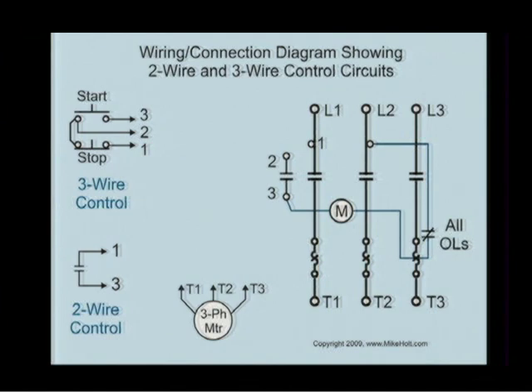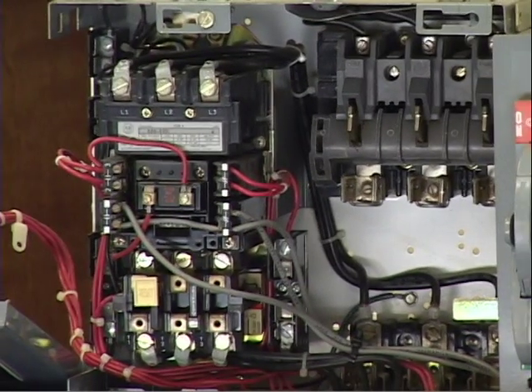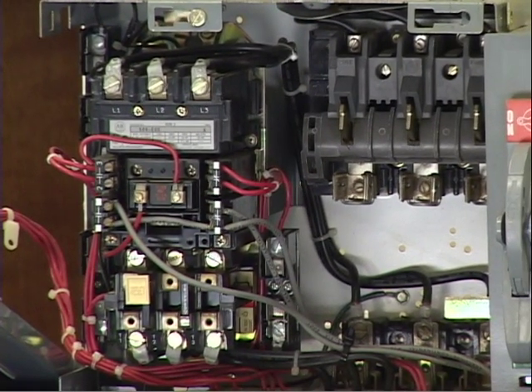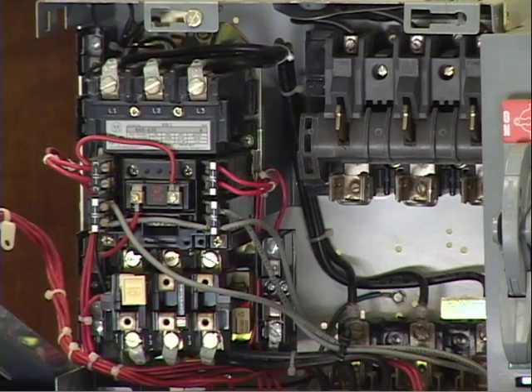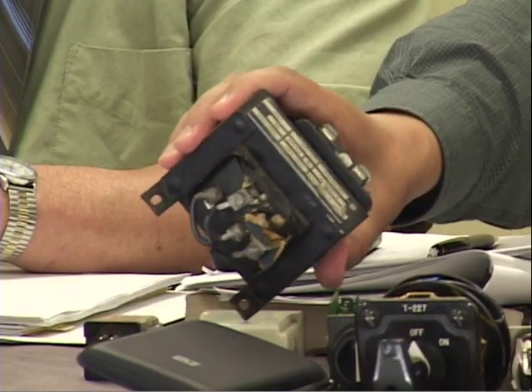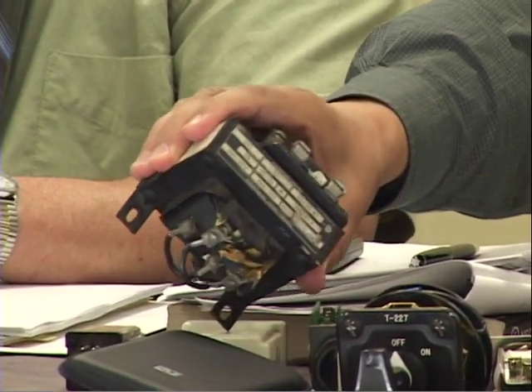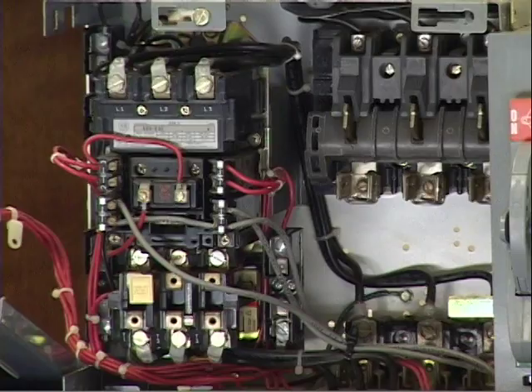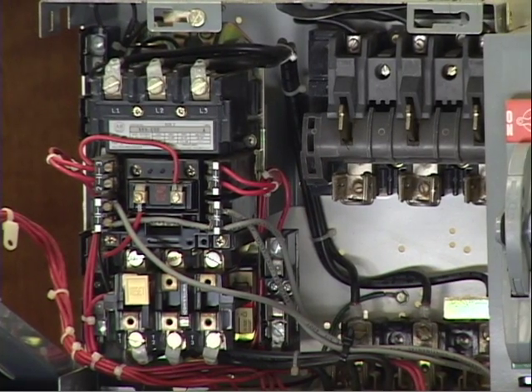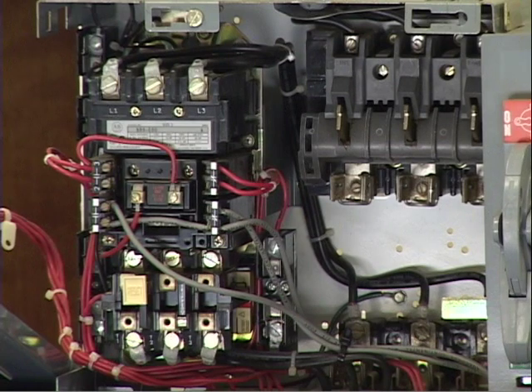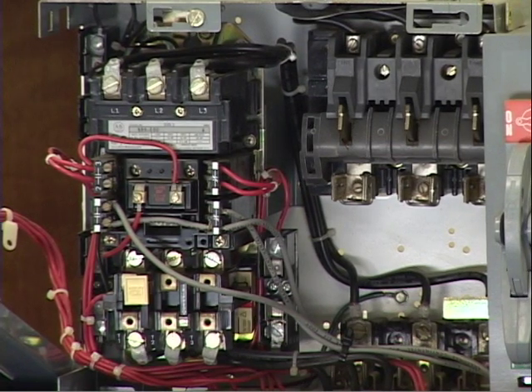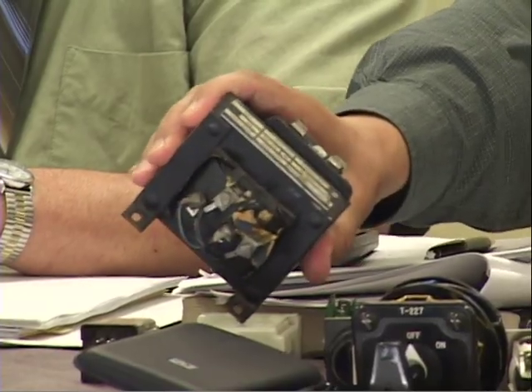Now, Dennis, we got something over there at the end of that table. Well, this is what Eric brought, basically an MCC bucket, and we were kind of hoping that there was a transformer in there, but there's not one in there. But Eric's got a transformer in front of him that would physically go inside this bucket. But wouldn't you have to get equipment that is designed to use a specific transformer by that manufacturer and to be installed in that equipment? Yes. You can't just start going in and dropping transformers in there.